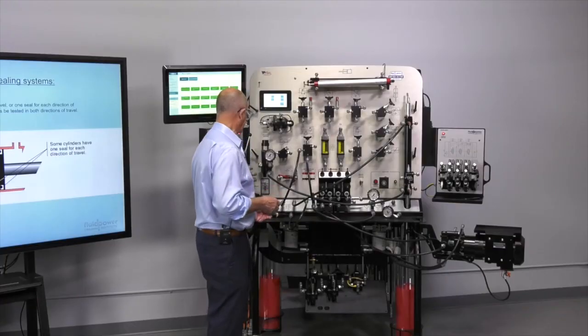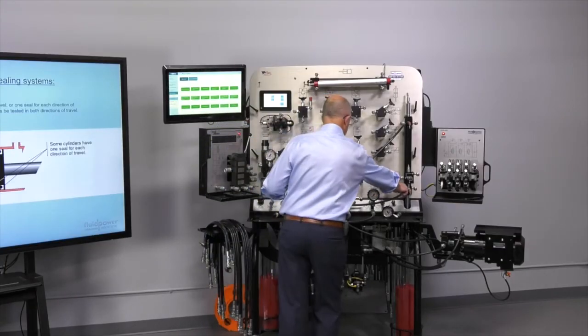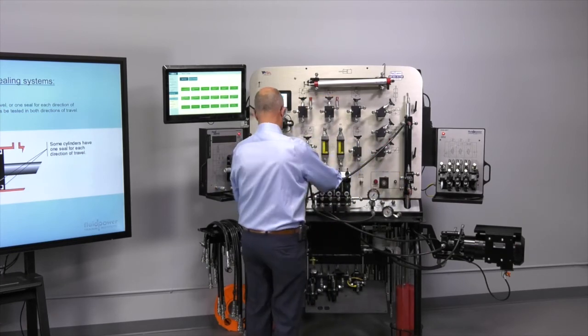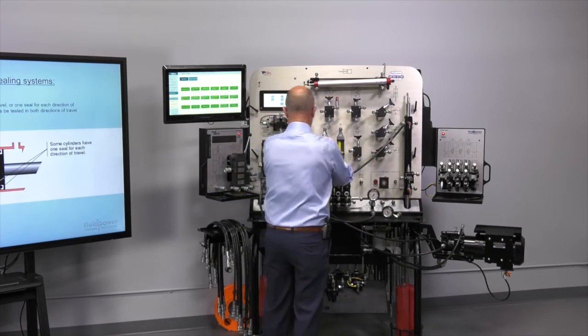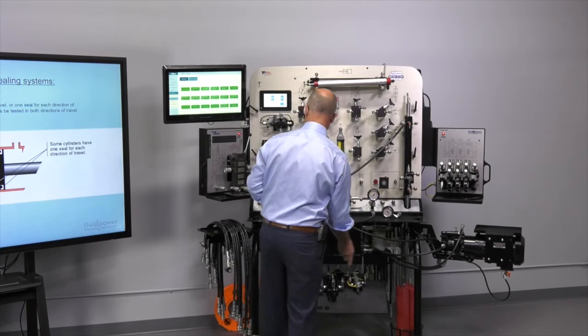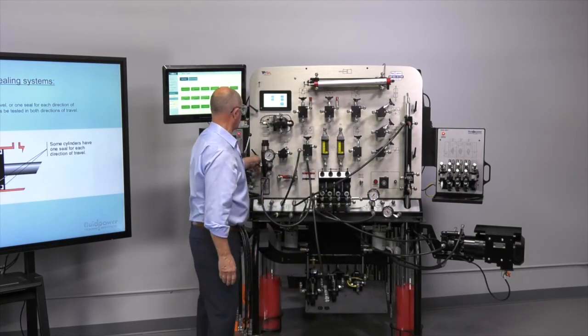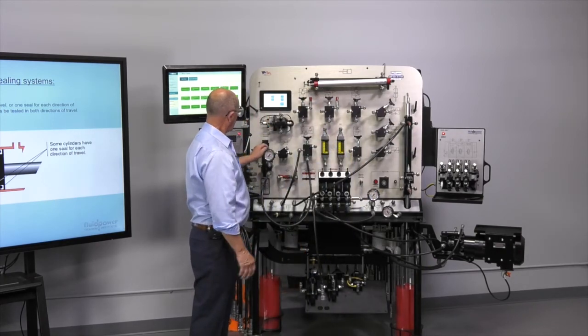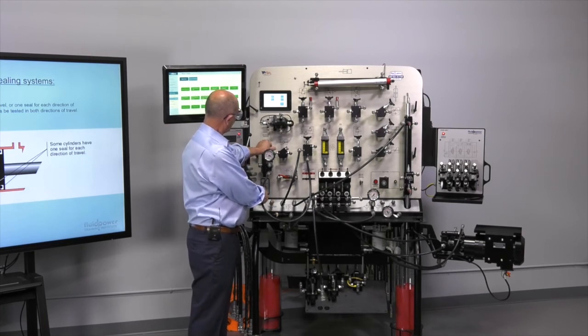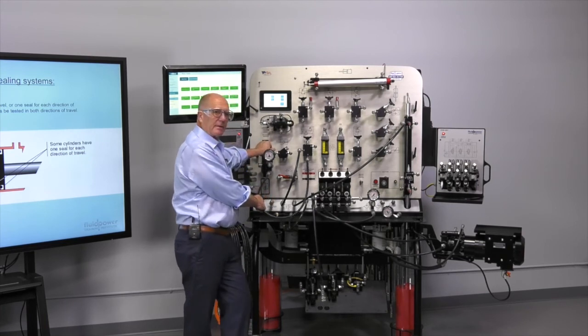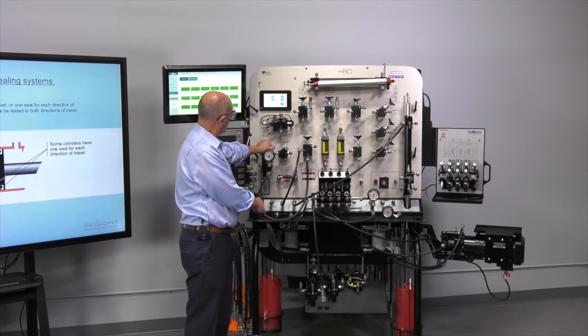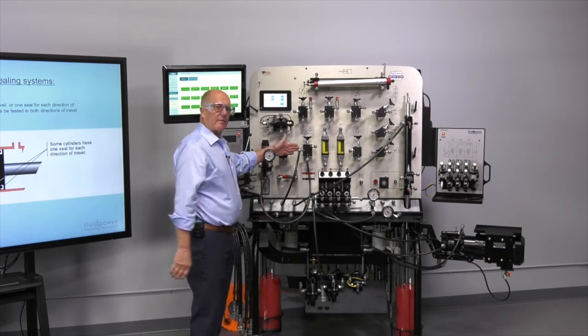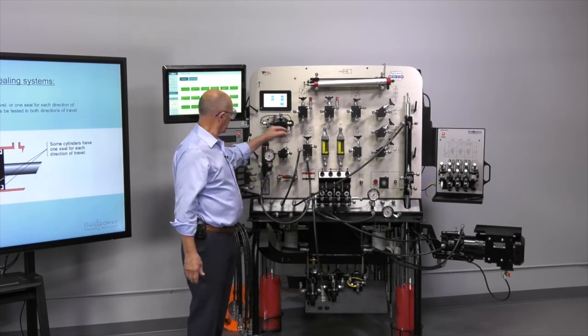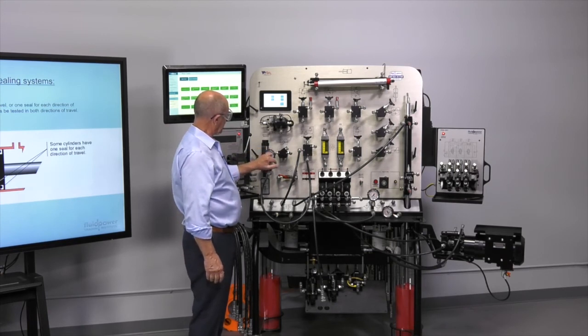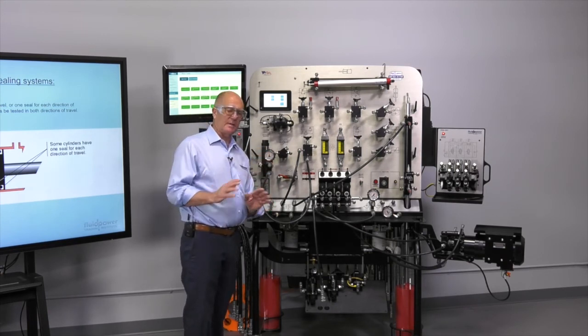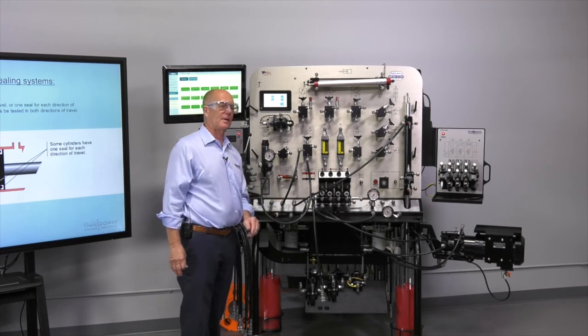So here's a pressure relief valve. I suspect the seat is leaking. And this is how quickly I can figure out the condition of the seat in this pressure relief valve. So here we go. I'm going to pressure in. And as you can see, I'm building pressure. It's going to drop off very slowly because it's a pilot operated relief valve. It's got a lot of moving parts. And so I'm seeing a slight decrease in pressure, but I did get resistance. The minute you get resistance, the component is a keeper.